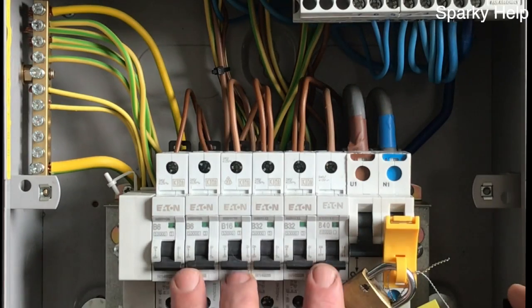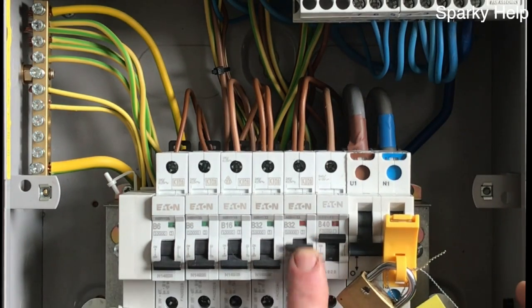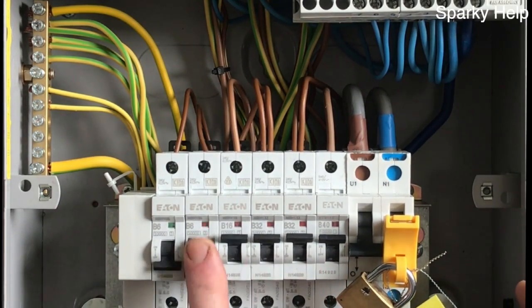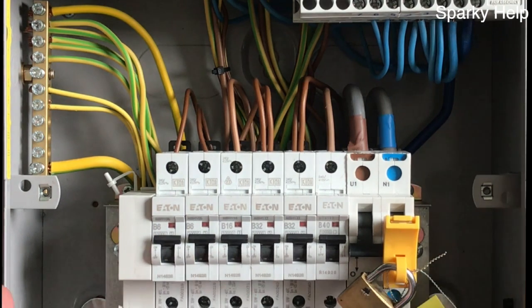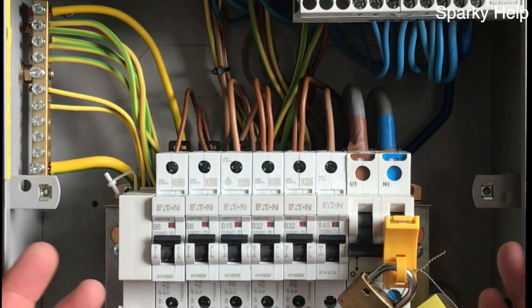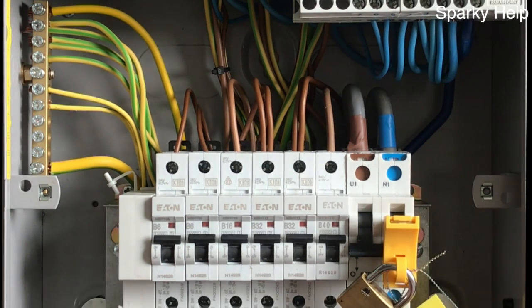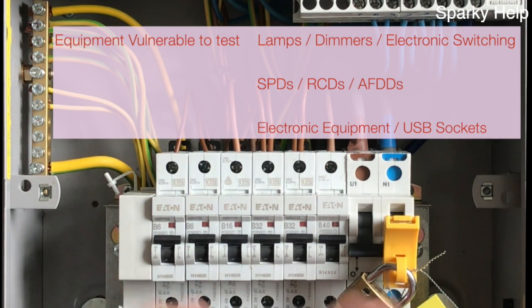What we do need to do is turn all circuit breakers on, because as I've said before, we're going to test a whole lot in one go. I don't have any RCBOs in this particular board, so therefore nothing vulnerable to test. I've already been round the installation and taken out anything vulnerable to test, such things as dimmers, and lamps we've already spoken about, but please have a look prior to doing it, because the last thing you want to do is destroy them. All the circuits are on, we now need the meter.